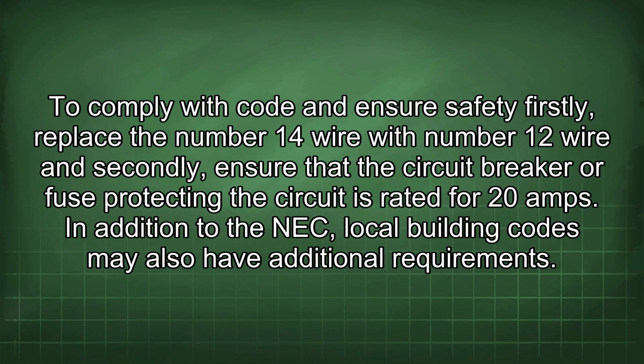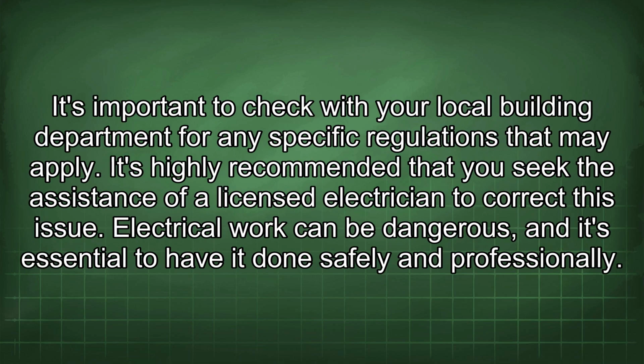To comply with code and ensure safety, firstly, replace the number 14 wire with number 12 wire, and secondly, ensure that the circuit breaker or fuse protecting the circuit is rated for 20 amps. In addition to the NEC, local building codes may also have additional requirements. It's important to check with your local building department for any specific regulations that may apply. It's highly recommended that you seek the assistance of a licensed electrician to correct this issue. Electrical work can be dangerous, and it's essential to have it done safely and professionally.